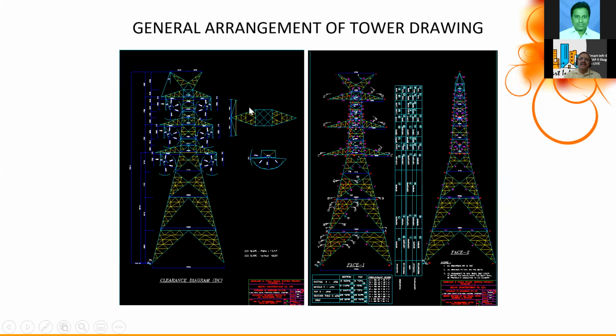This is the electrical clearance I was talking about - this is the insulator jumper, and this is the swing angle. In plan also, we check the electrical clearance between the conductors. These are all the arcs of the minimum distance to be maintained between the steel parts and the conductor, which we maintain.